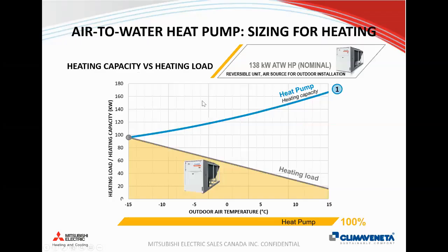So that was supply temperature and the operating envelope. And the other consideration that we need to keep in mind is also how the capacity will change over time. So if you look at any air-to-water heat pump manufacturer's literature, we'll publish nominal capacities based off the AHRI 550/590 standard. So whenever a manufacturer publishes standard conditions, this is rating the heat pump with the capacity that's available, typically around 8 degrees Celsius. So if we're looking at our heat pump capacity at 8 degrees Celsius, this is our nominal value. So in this example, this is a 138 kilowatt nominal heat pump.